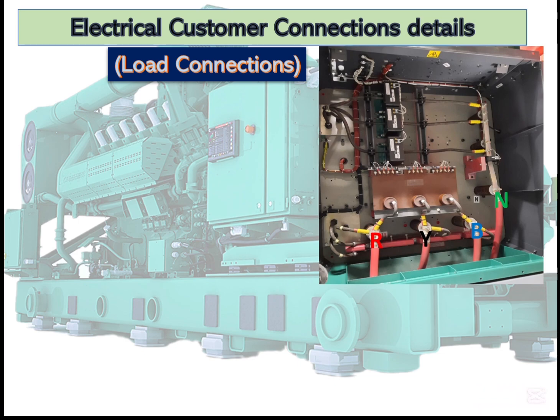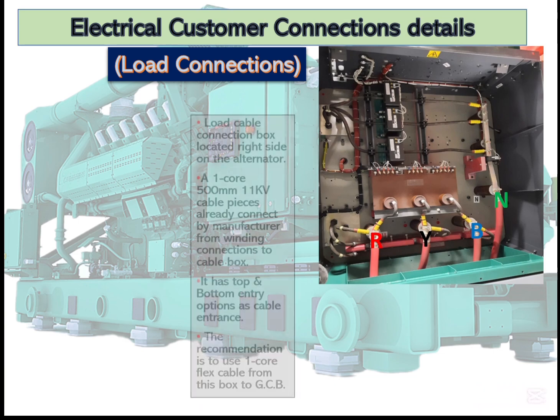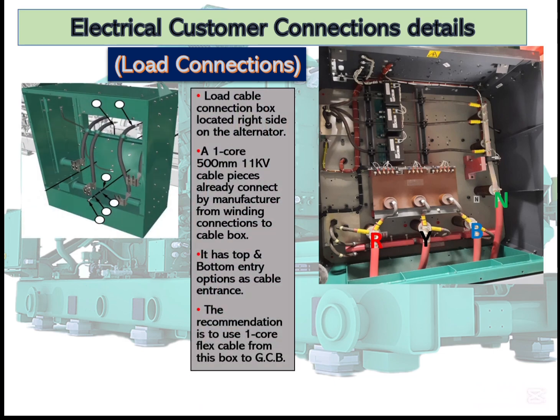Then Cummins introduced a connection box. This is a connection box that ties with the alternator cover. Then they provide small short pieces of cable. This red cable we can see here. So from the alternator terminals, the 4 cables come to this terminal box or connection box, from where we now connect our load cables. Let's have a look.